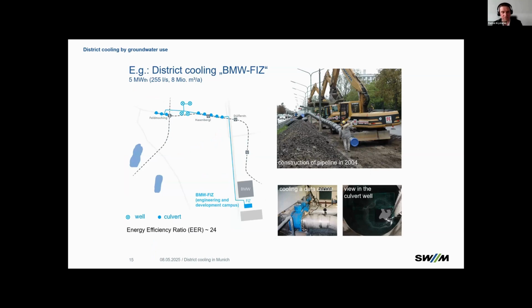As you can see here, one of our systems was the first system we installed, in 2004. That's BMW, where they have a high cooling demand of around 5 megawatts for their data centers. That's around 250 liters a second. And we extract the groundwater by culverts and wells, and have a pipe system of around 5 kilometers to the data center. And it has run for around 20 years with no problems. Very good system. As you can see on the lower left, it has a very high energy efficiency ratio, around 24. That's because we don't need chillers, we just supply the data center with groundwater, and there's only energy needed for the pump and nothing else.